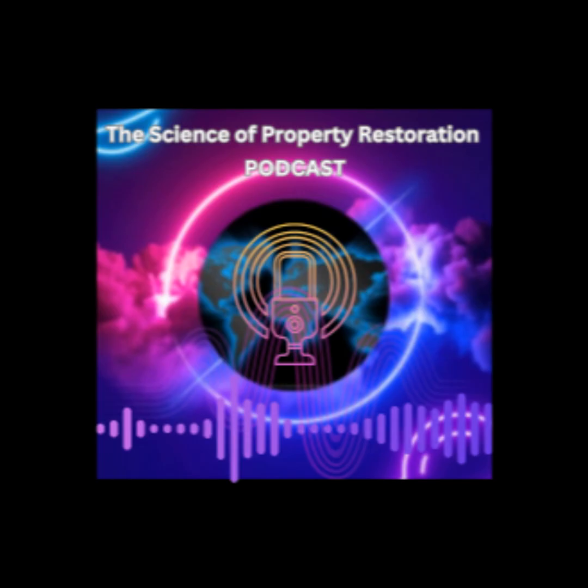That makes a lot of sense, especially with the GUV-222 being whole room irradiation. It's shining directly on the floor and lower walls. Precisely, whereas the upper room GUV-254 is mostly just hitting the air high up. It's not really illuminating the main room surfaces in the same way. So the implication is huge. It means the design and placement of the GUV unit, whether it shines on surfaces or not, might be more critical for these OVOC byproducts than just the UV wavelength itself. That seems to be what the data suggests here. Direct surface irradiation seems linked to this effect.